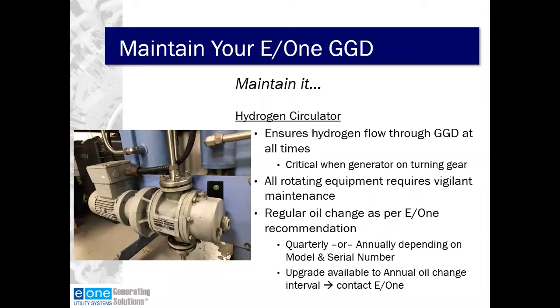Depending on the model and serial number of your unit, it has either a quarterly oil change requirement or an annual oil change requirement. If you're uncertain, call into our tech hotline with your model and serial number. We'll let you know where you are and what the program requirement is. And on our more recent units, we've evaluated several different oils that provide a 1-year or annual oil change interval. That oil we can make available to you, and there's a software change that can be provided so that the oil timer can be extended to the 1-year oil change interval.